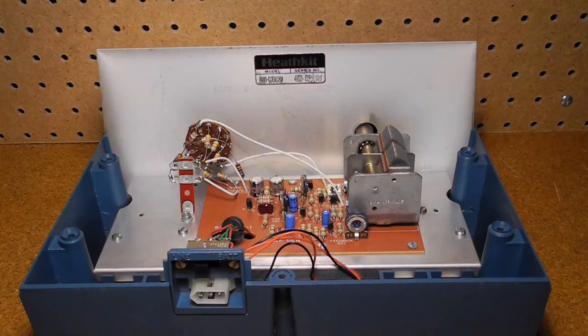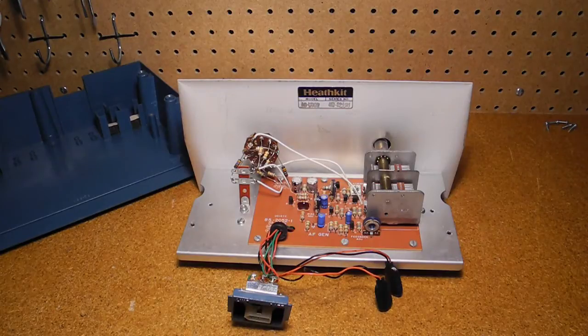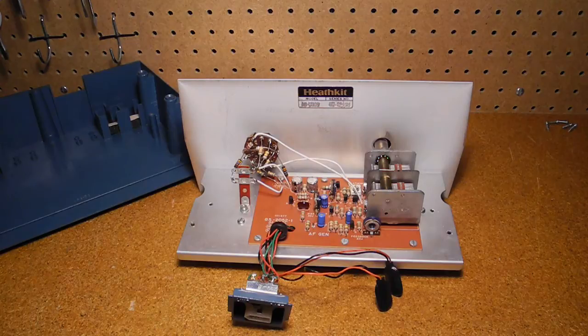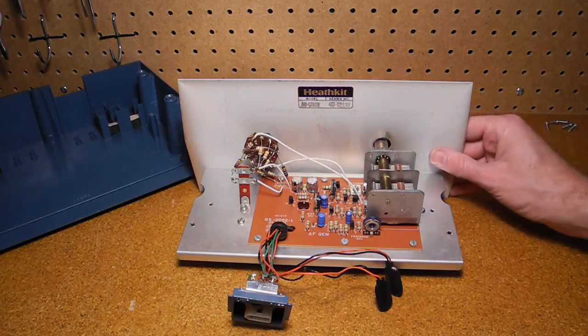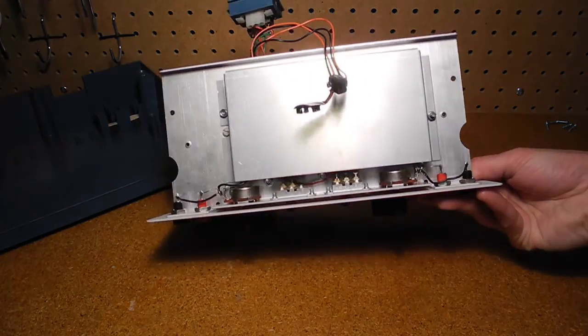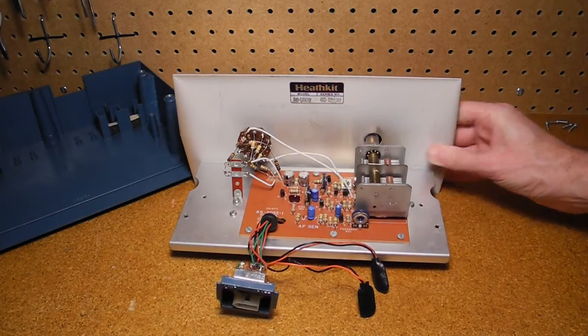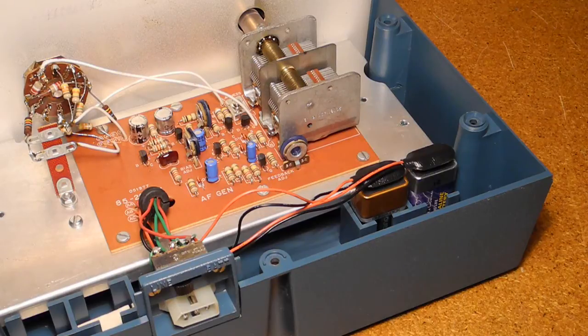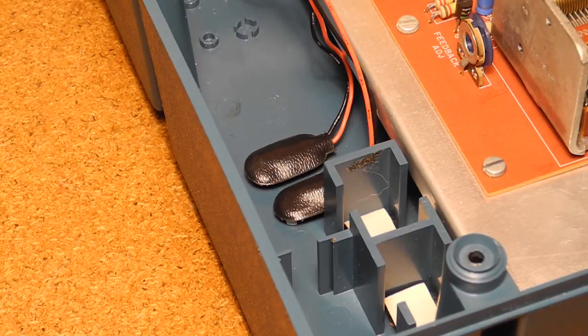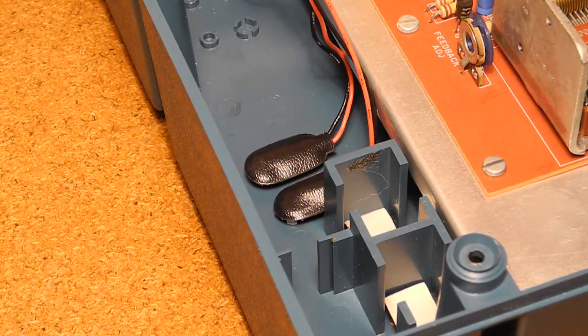Circuitry is contained on one printed circuit board, as well as some point-to-point wiring to the controls. The PCB is mounted on a metal chassis, which in turn connects to the bottom half of the case. The chassis and front panel can be removed by the removal of two screws. There's a metal shield which covers most of the bottom of the PCB. There are clips and holders for the two 9-volt batteries when the unit's running on battery power. When using an external power supply, the battery clips can be snapped to the bottom of the case to avoid having them short to the internal circuitry.